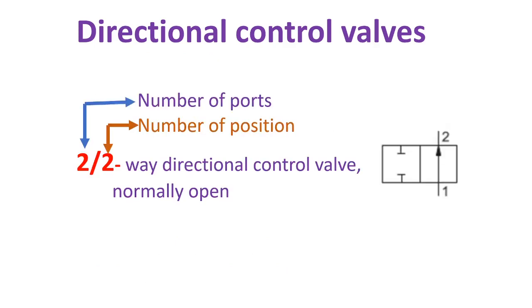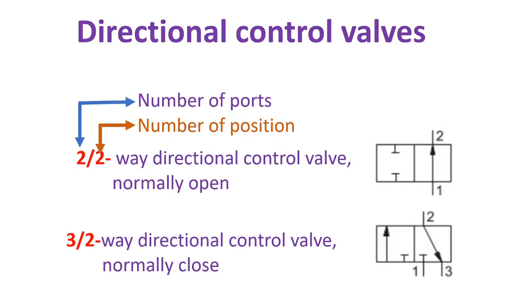This is one of the examples of directional control valves. The first letter represents the number of ports and the second letter represents the number of positions. This valve is a two two-way directional control valve normally open. The next one is a three two-way directional control valve normally closed.